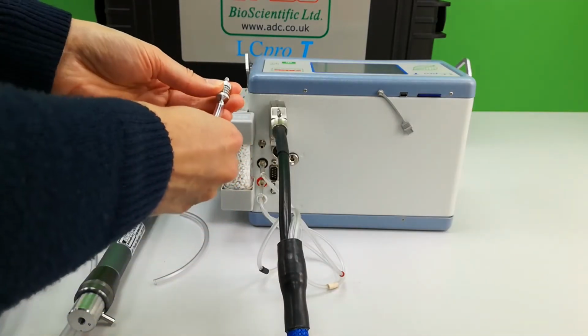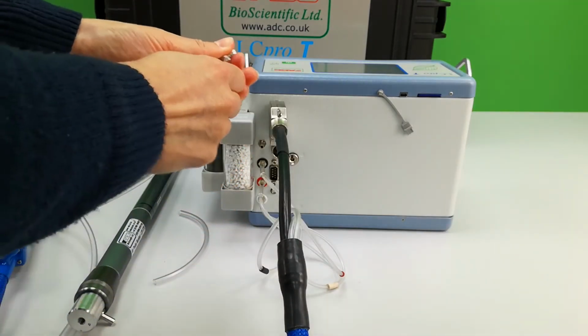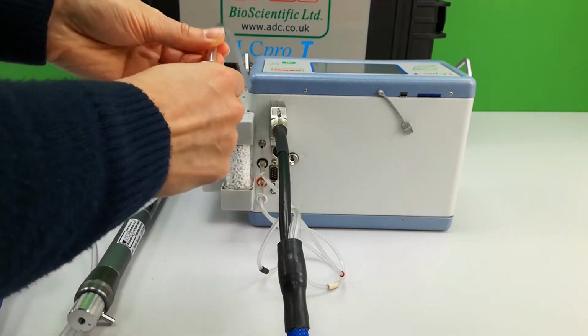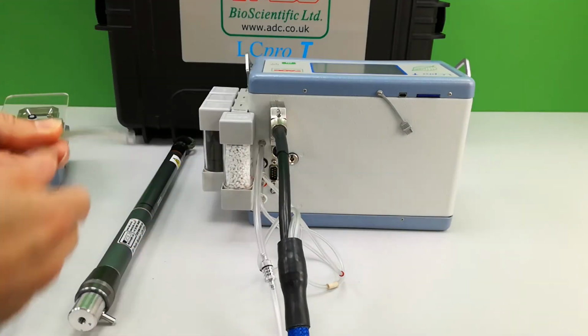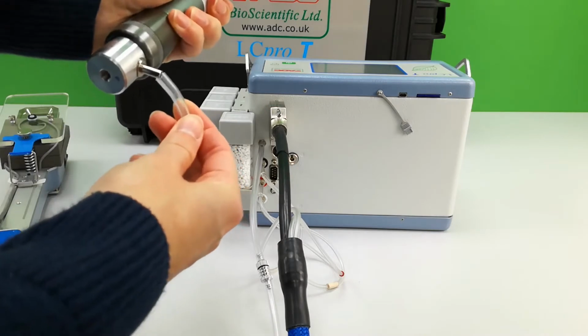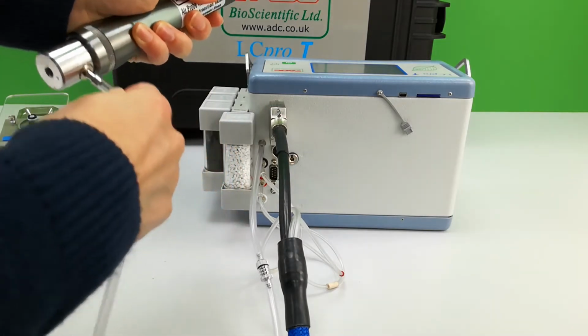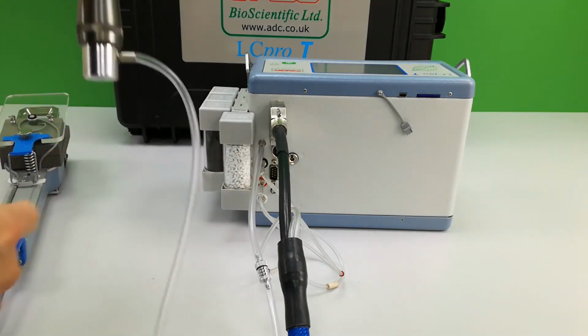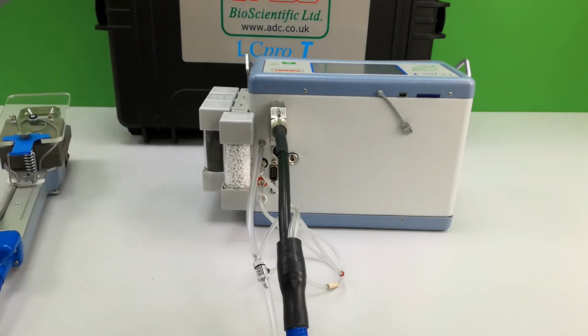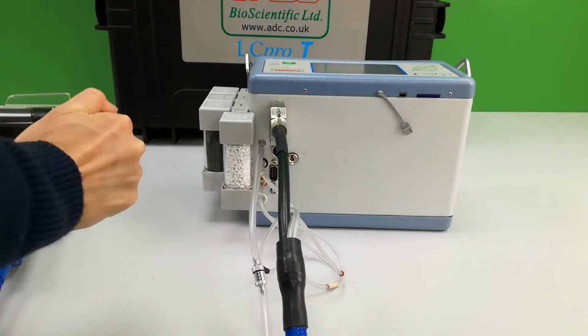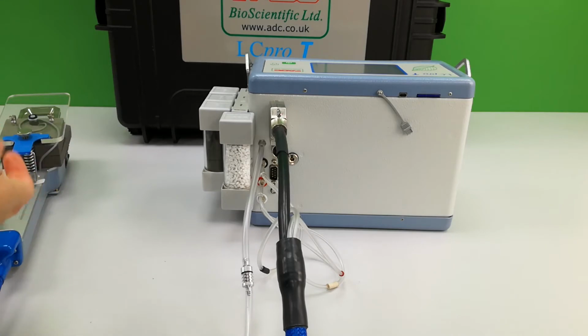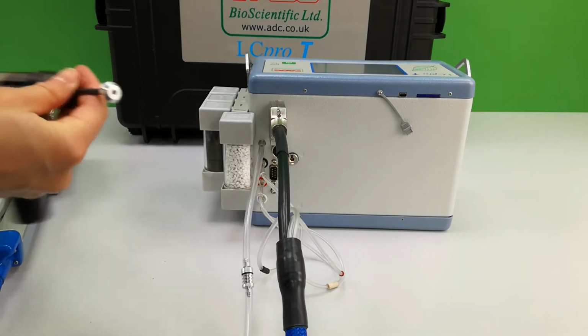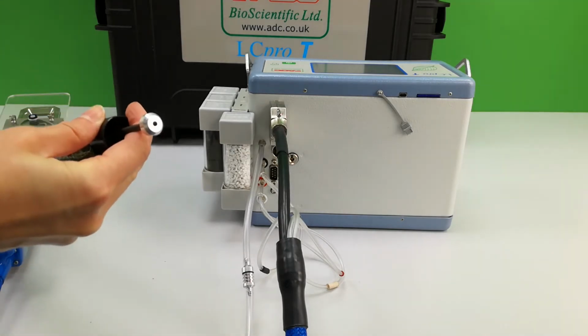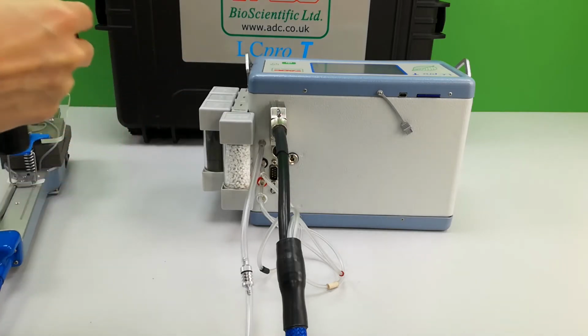Use the metal filter from the spares kit to fit into the tubing close to the LCpro T console. This will prevent debris from being drawn in. Attach the spike to the base and push into the ground. Unscrew the lid and lengthen the air probe to its full extent, around 2 meters. Ambient air will be drawn down into LCpro T from the top of the probe.